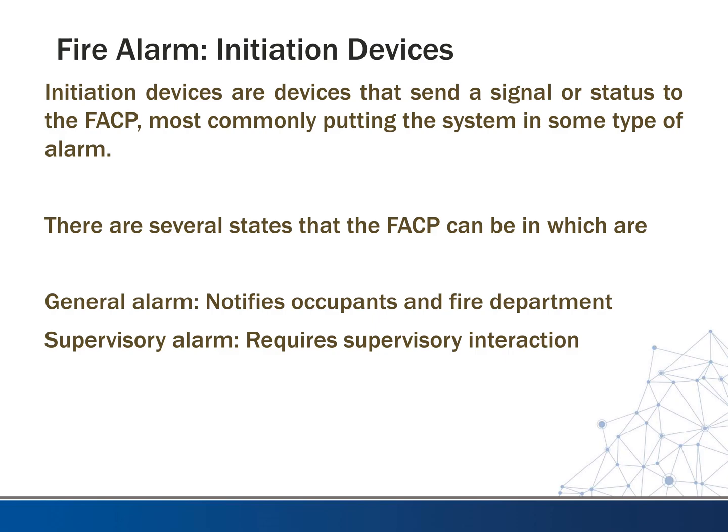If we detect smoke in a guest room, we do not put it in general alarm, but in supervisory alarm. We put an annunciator panel right at the check-in desk, where someone must be present 24 hours a day. They'll see the supervisory alarm and can call up to the room or walk up there to check if there's actually a problem. It could be someone who burned something in the microwave or toaster — we don't want to empty the entire hotel for that. If they see a real problem, they can pull the nearest pull station to put the whole system in general alarm.